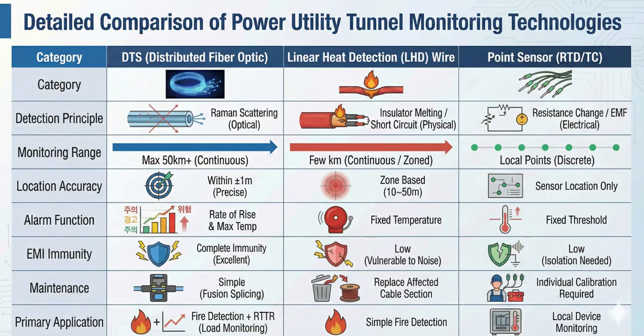A comparison table for utility tunnel monitoring shows that DTS offers long coverage, high location accuracy, and analytics-based alarms such as temperature and rise rate detection. LHD is structurally simple but limited to zone-level detection, and point sensors are precise, but can be burdensome to deploy and maintain at scale. Considering EMI immunity, maintainability, and application scope, DTS emerges as the most advantageous overall choice, especially because it supports not only fire detection, but also RTTR and asset management.